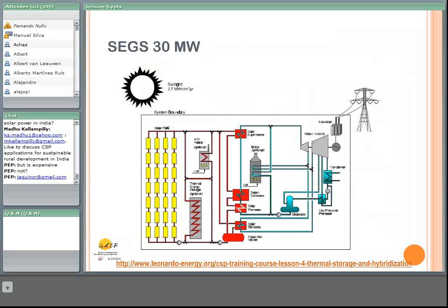We can integrate the backup fuel in different ways. We could include an auxiliary or secondary boiler, which can be used to generate steam when there is no solar energy input or it's insufficient. So we can have the fossil, normally natural gas, boiler on the steam side, or we can have a heater on the heat transfer fluid side, on the oil side. This is the case for most of today's parabolic trough plants.